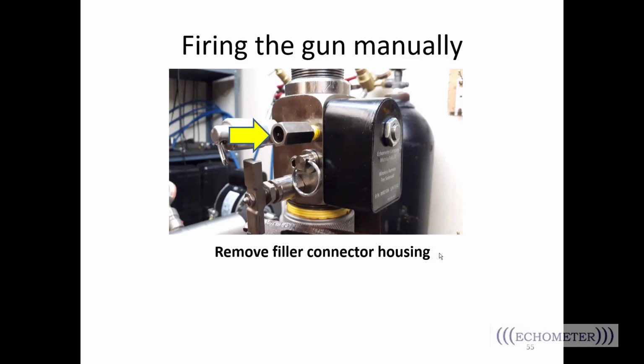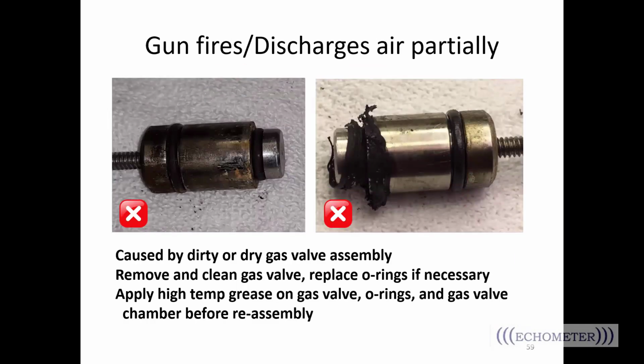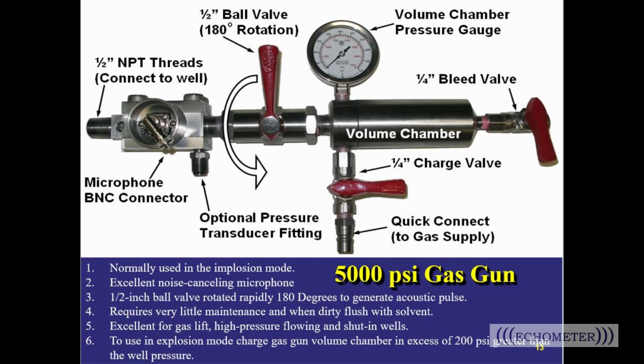Is there a limit on the differential pressure when imploding into a 5K gas gun in order to not damage anything? Is there any limit when you're shooting an implosion pulse? We recommend trying to use no more than 1,000 psi of differential pressure for the 5K gun. But it's safe to shoot at a higher pressure, but there's a nylon bushing in there on the firing valve, and if you use a really high differential pressure, you may have to replace that valve because that nylon will be damaged and leak.